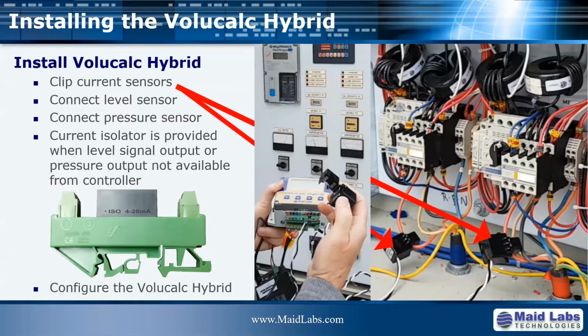But we have an adjustment on the Volucalc so that we can change the actual rating of the current clamp so that they get the highest accuracy at 15 amps. So we have a switch for that, and we have bigger current clamps that can go up to 1,500 amps. So it's a matter of what size of pumps you have. Many municipalities use our instrument as a diagnostic tool that they move around, because it is so simple to install and move around, and it doesn't take a lot of space, so they just leave it on the bottom of the control panel.